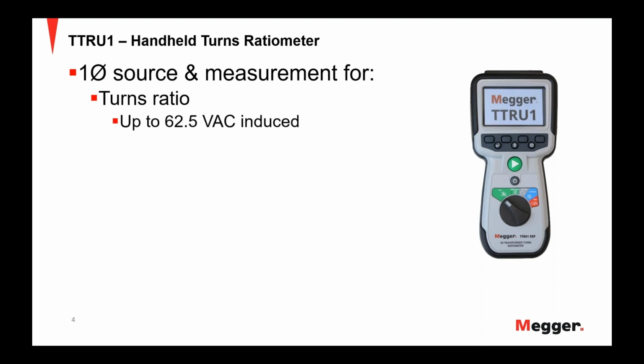The TTRU-1, as its name implies, is a single phase source and measurement turns ratiometer that has up to 62.5 volts induced, plenty enough voltage for any size distribution transformer you may be testing, up to 1 or 5 MVA. With an accuracy of 0.05%. And the accuracy that's required when you're doing turns ratio testing is 0.5. So when you get results with the TTRU-1, you can be confident that you can trust them, whether they tell you the transformer is failing or it's passing.